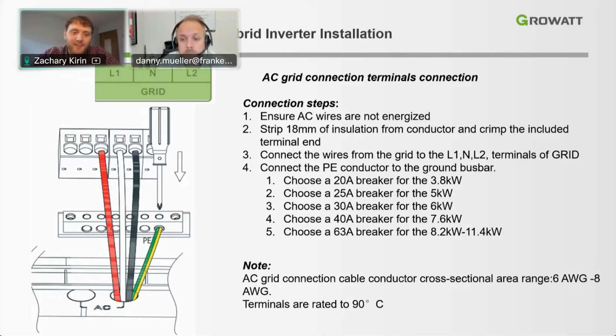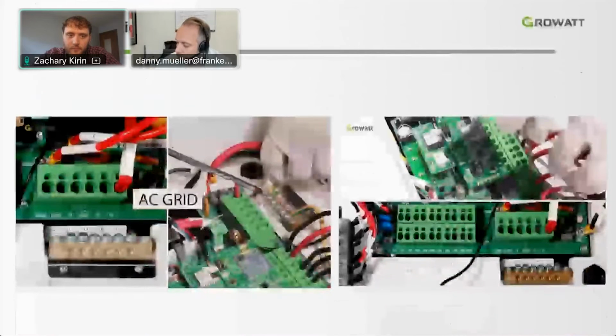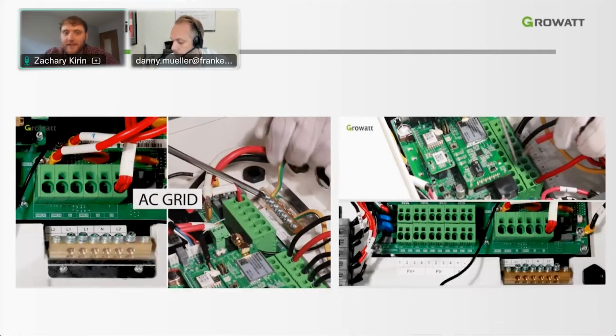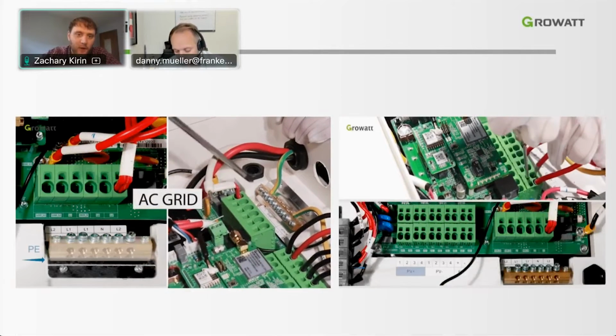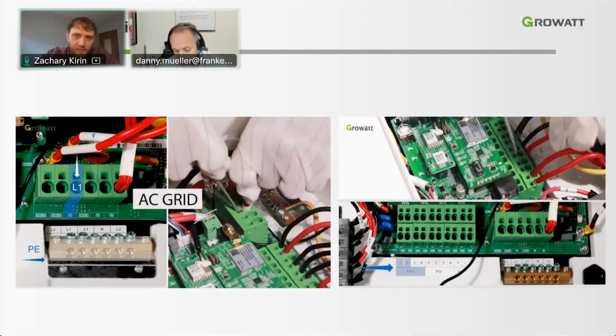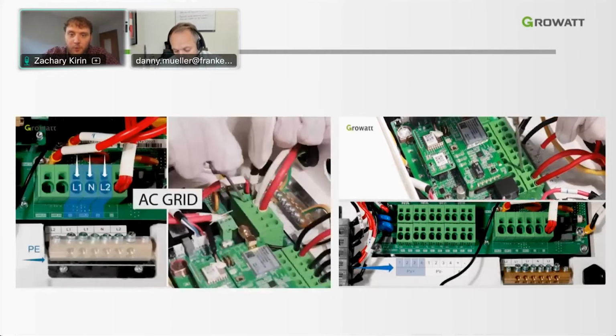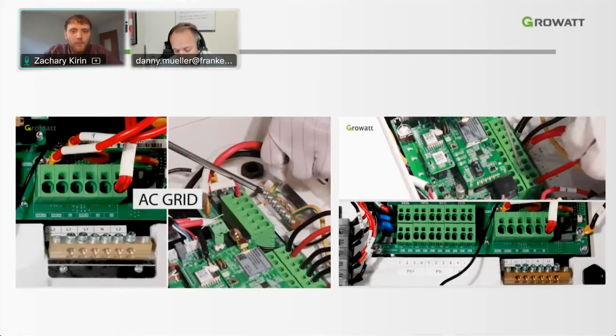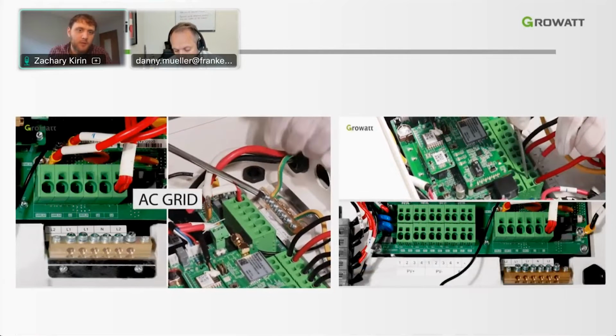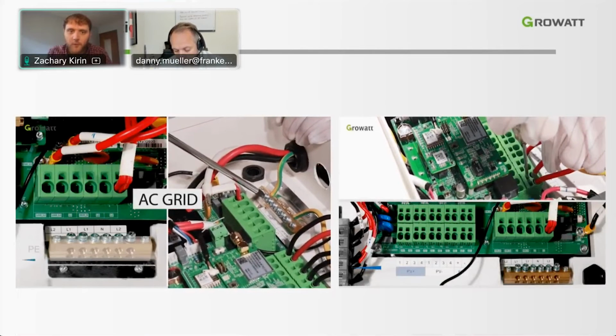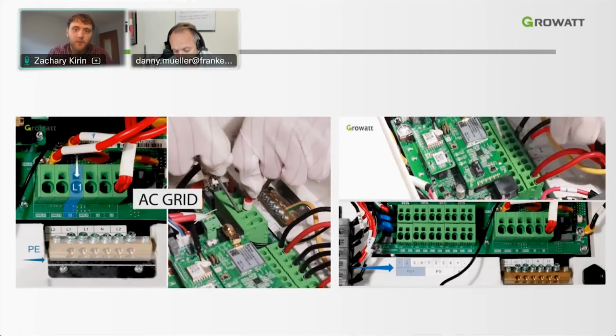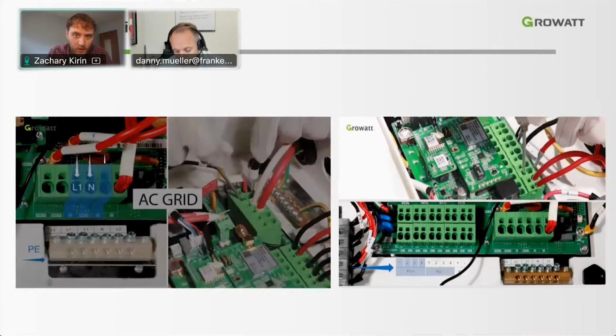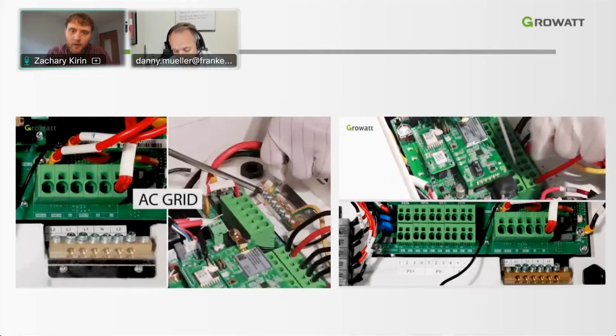Excellent. So the AC grid conductor cables, 6 gauge to 8 gauge, relatively common, and the terminals again are rated to 90 degrees. This is a little slide that just depicts exactly how the conductors are input to the terminals. So we really made this an easy process. We didn't want to overcomplicate it with torquing requirements and things of that nature. So instead, we went with a simple clamp connector.